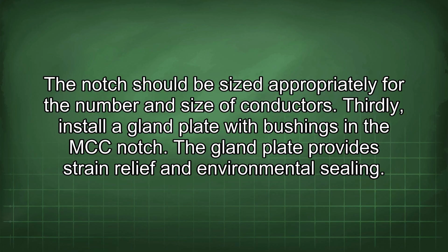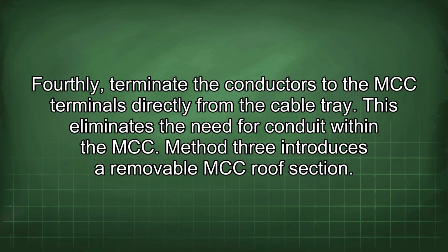Thirdly, install a gland plate with bushings in the MCC notch. The gland plate provides strain relief and environmental sealing. Fourthly, terminate the conductors to the MCC terminals directly from the cable tray. This eliminates the need for conduit within the MCC.